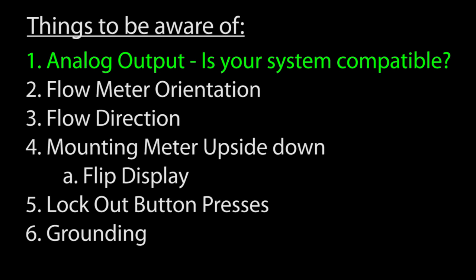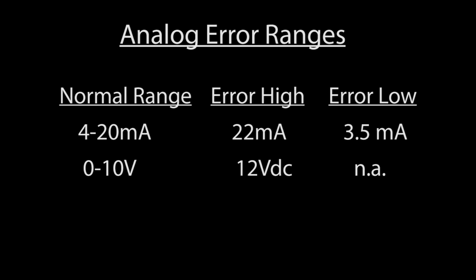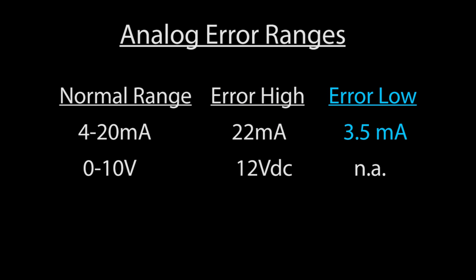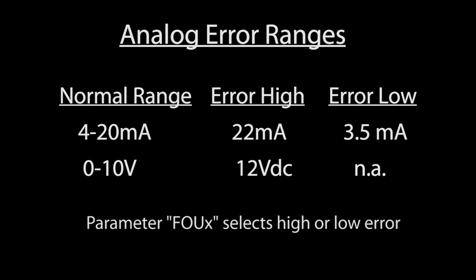First, you can specify what you want the analog output to do in case of an error. It can go to a high value, a low value or just output the measured value. The main thing to be aware of here is you need to make sure your equipment can handle the current and voltages outside of the normal 4 to 20 milliamp or 0 to 10 volt range before using these options.